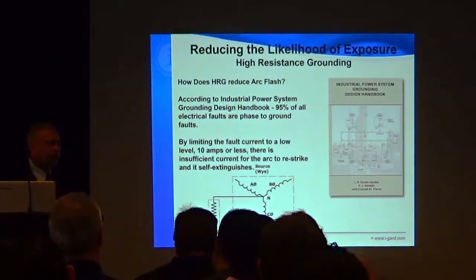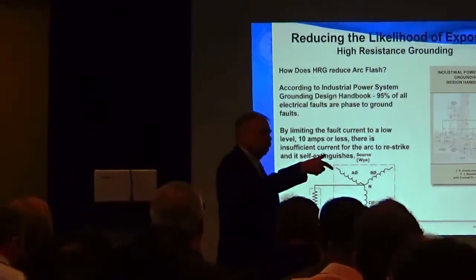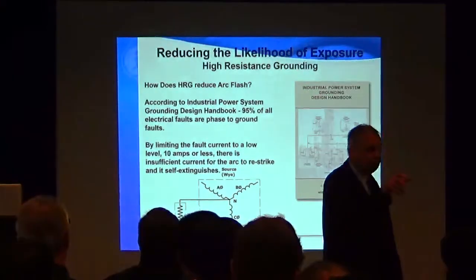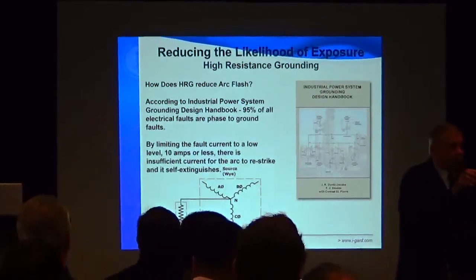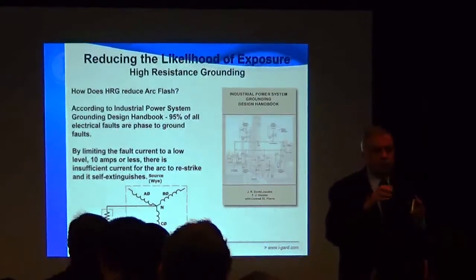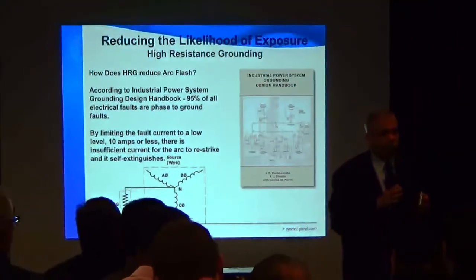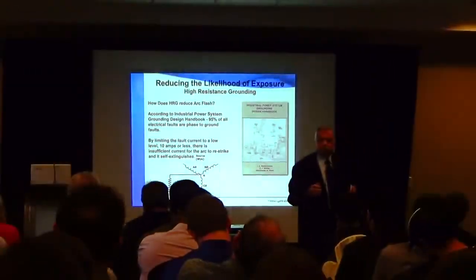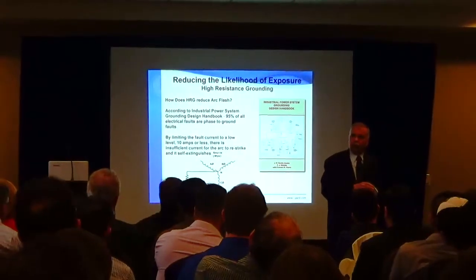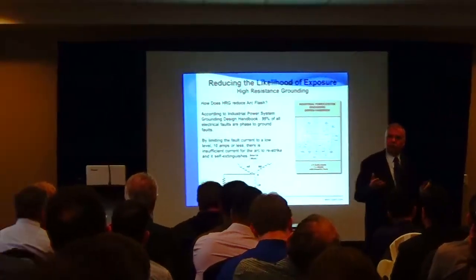If you don't allow the line to ground fault to escalate and go further, because that arcing, the ionized gases kind of balloon as they expand with the temperature, the adjoining phase now gets connected, and now you have a line to line to ground fault. So people ask the question, well, how long does this take for this migration to occur?